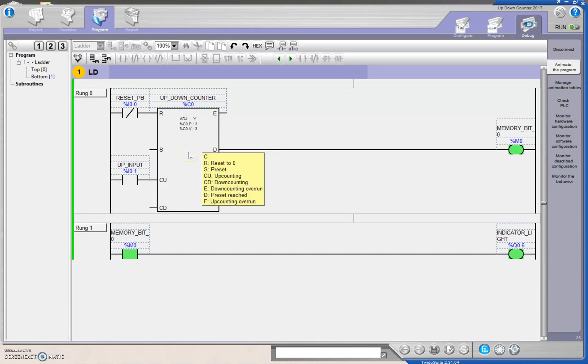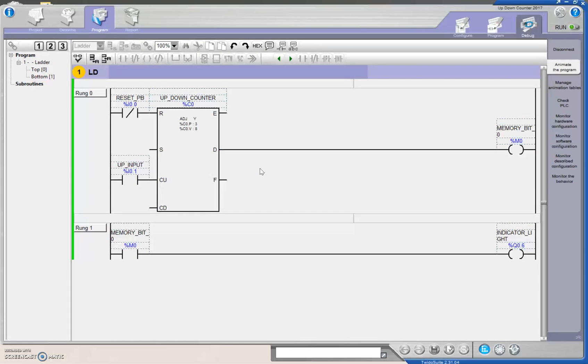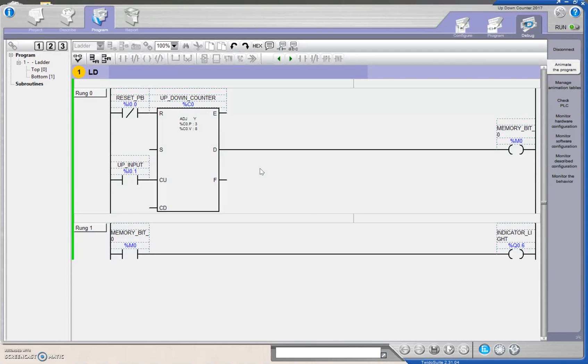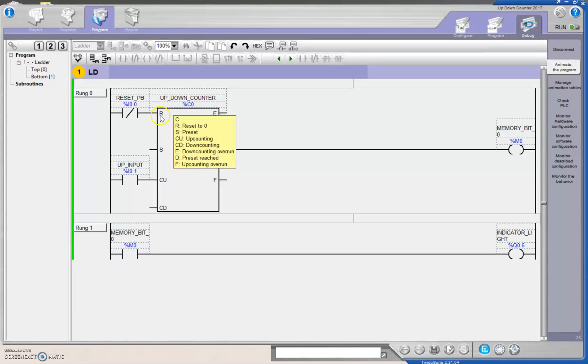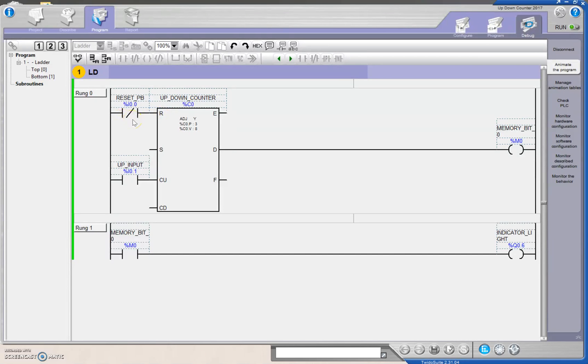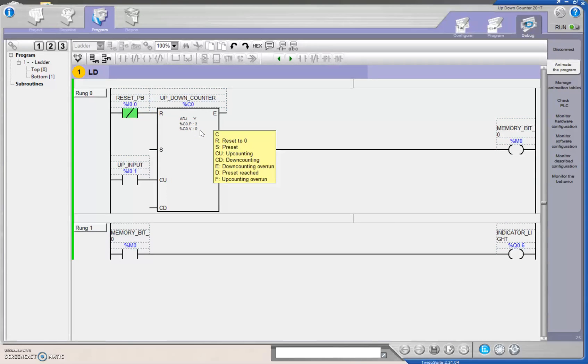So I can keep incrementing though. I can keep going up and up and up. So we'll have to do something later on to take care of that and limit the value to just 3, because I can keep incrementing it up to like 9,999, right? So we'll have to put something in later on to deal with that issue. But for now, we're just looking at how this counter works. I now need to reset it. So I'm going to press that normally closed push button, which will stop the 24 volts going to the input. And you'll see that this value goes right to 0 as soon as this is true. Beautiful. At that point, my indicator light turned off.